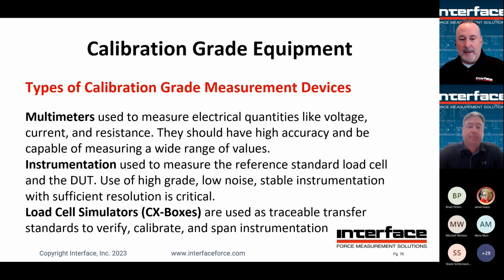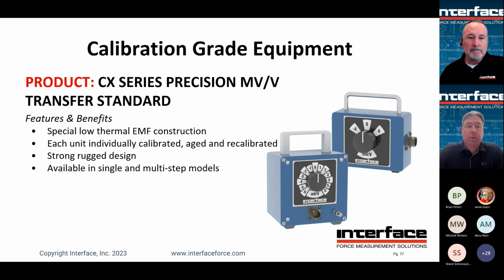And then also transfer standards or load cell simulators, which are commonly used to calibrate your instrumentation, so it inputs known and very precise millivolt per volt inputs into your instrumentation. There's an example of the transfer standard. Each unit is individually calibrated, aged, and then recalibrated. It has a strong, rugged design and is available in multiple step functions.